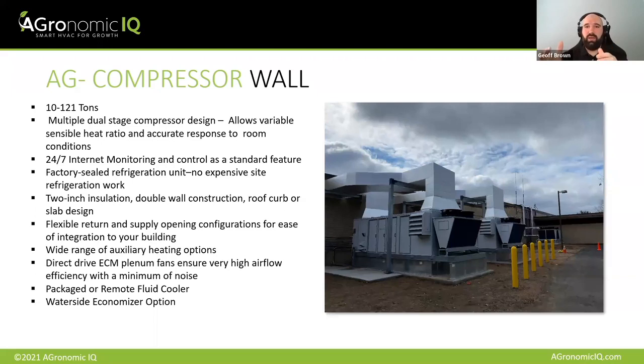Again, designed for the cannabis market, designed for operating in a high enthalpy environment in the cold or the heat. And so when I say a high enthalpy environment, one of the challenges with standard rooftop equipment is you've got a box on the roof, and if you turn that box off and it's not designed for it, well, that box is going to get wet because the box is going to be cold, there's no air flowing through it, and you're going to have condensation problems in it. And again, this is one of the challenges with on-off control of typical HVAC, is you end up with a bunch of other problems that sort of come out of it.